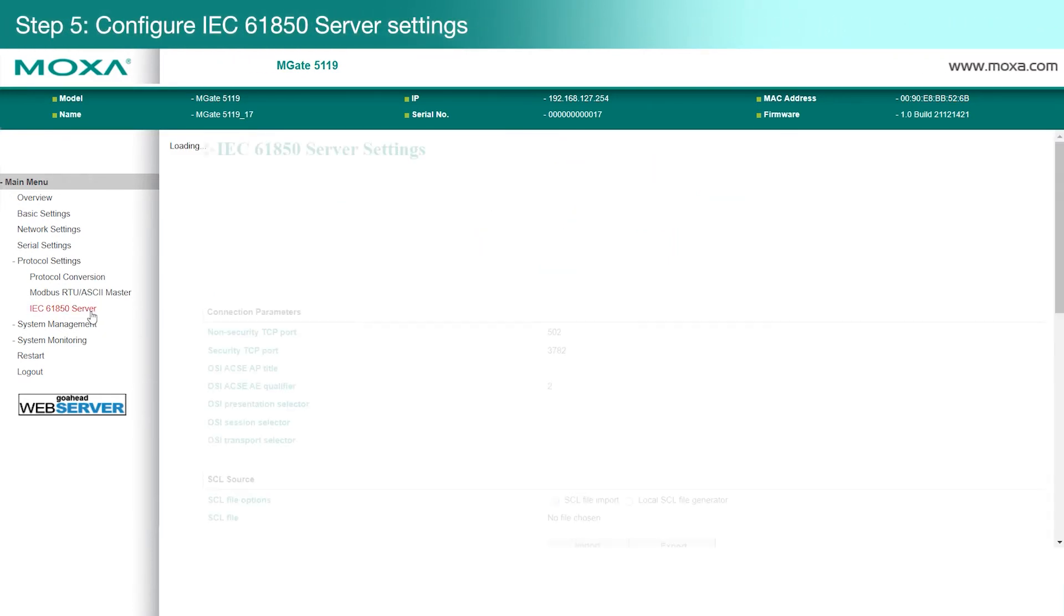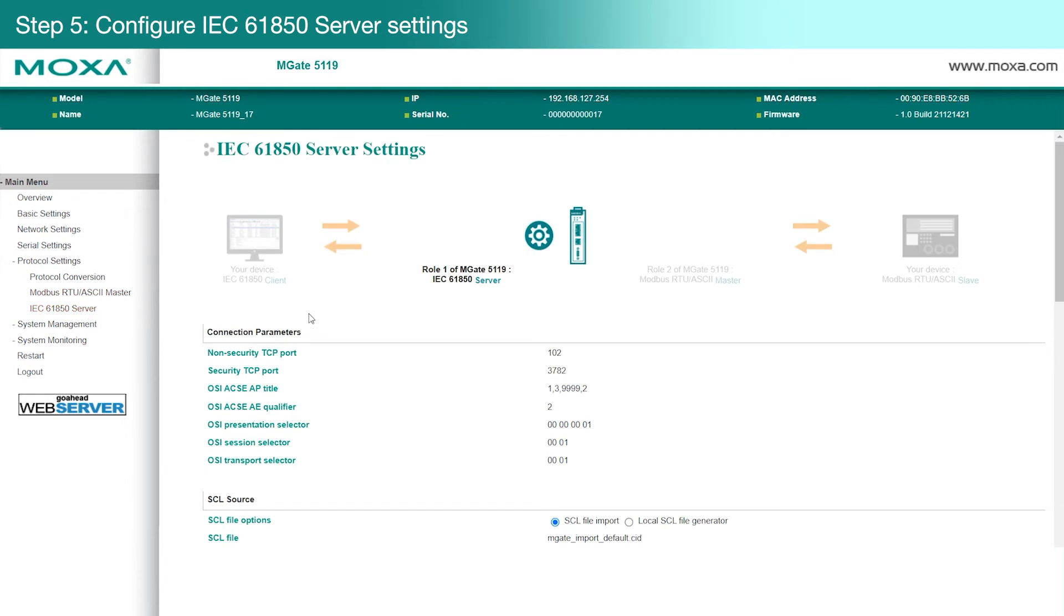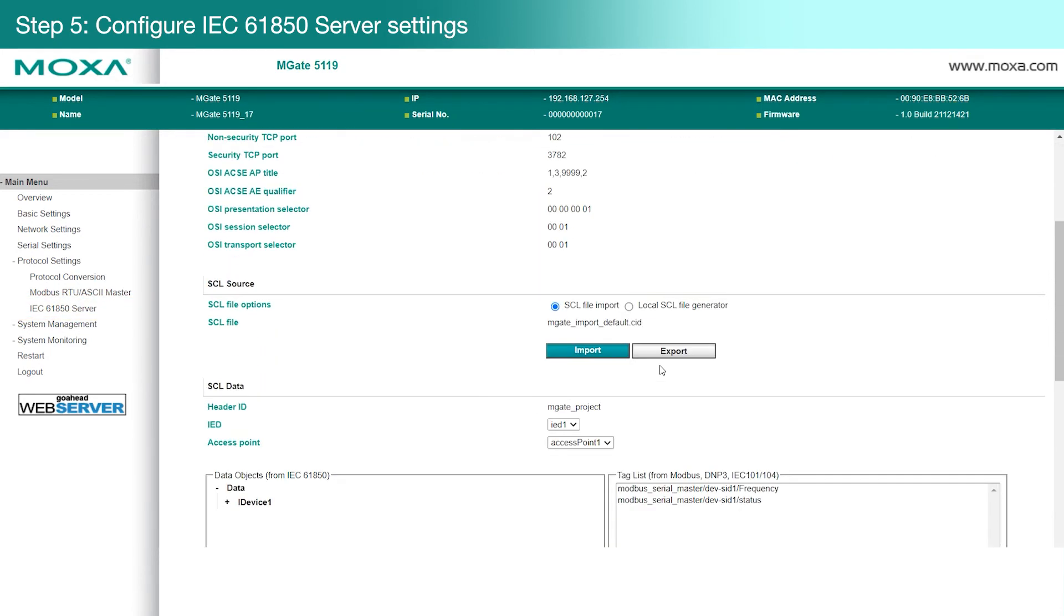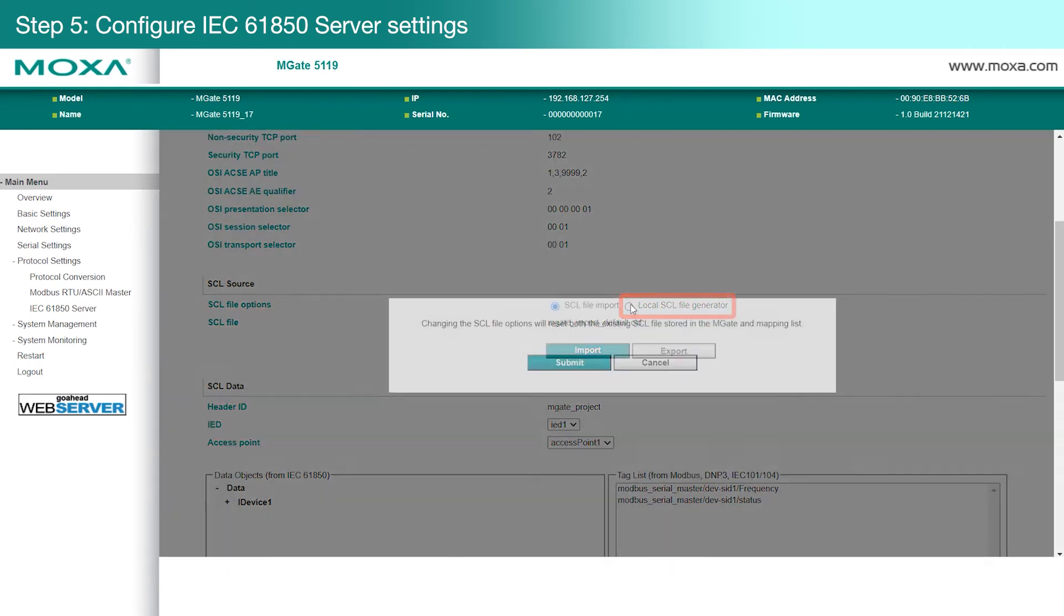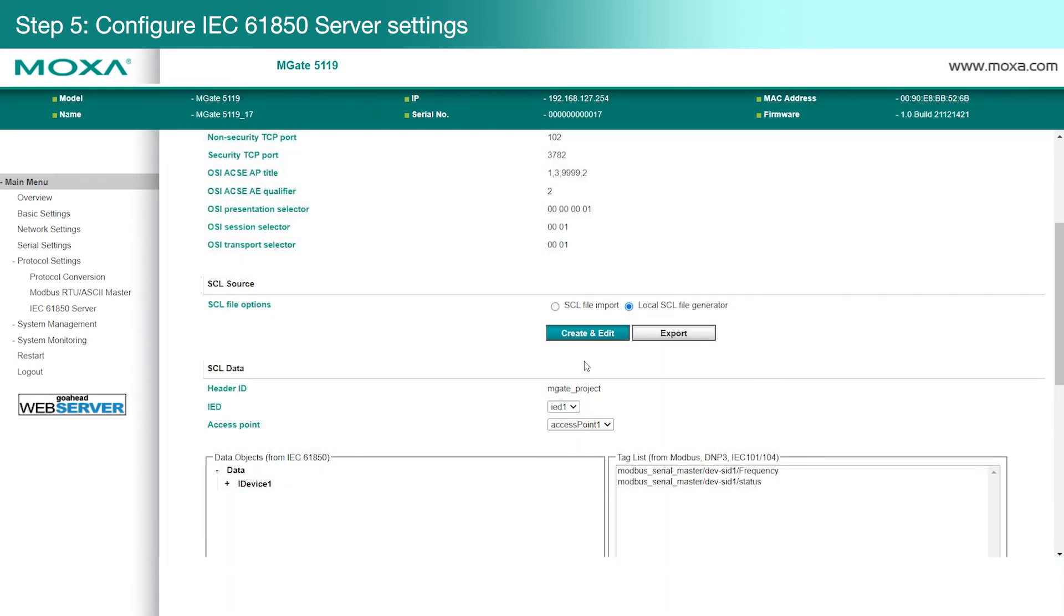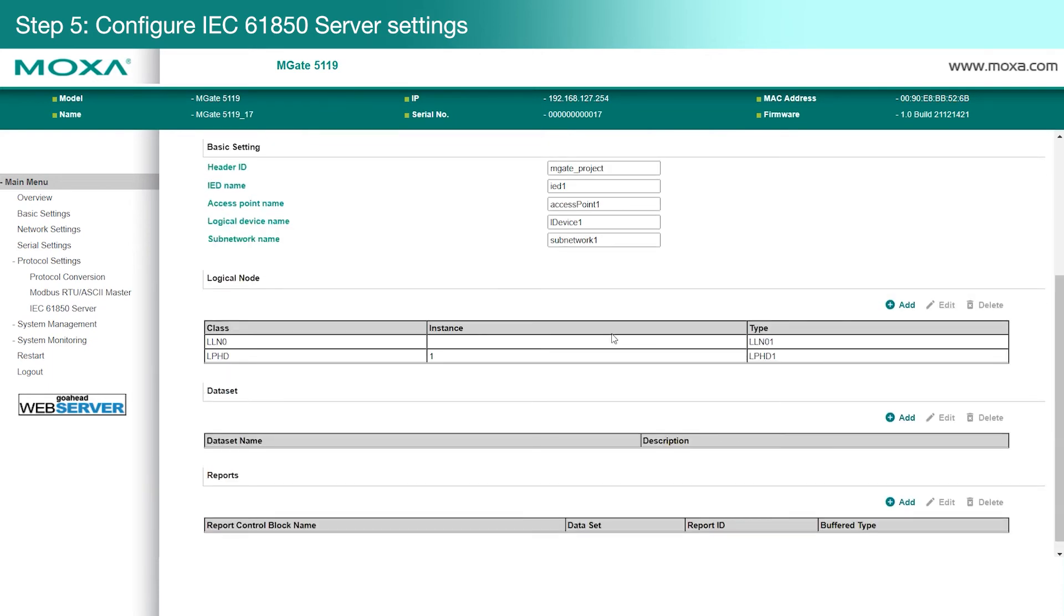The MGate acts as an IEC 61850 server. Now, normally, you would need to create an SCL file using a third-party tool, but the MGate lets you create an SCL file directly to save time and simplify the configuration process. On the IEC 61850 server page, we're going to select Local SCL File Generator. Click Submit. Then we'll click Create and Edit to access the SCL file settings page.